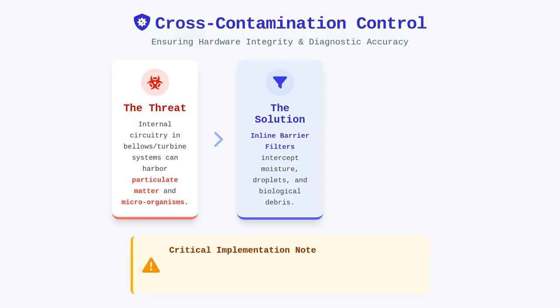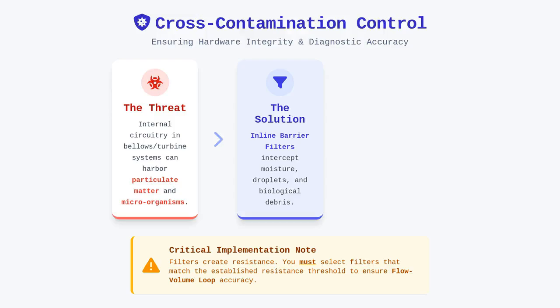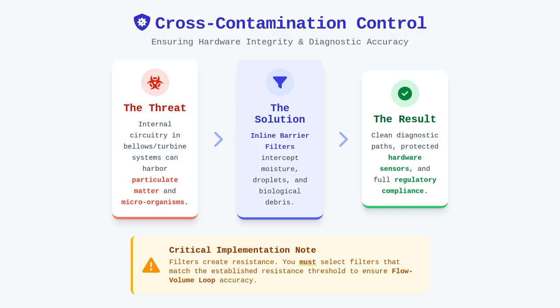It is important to remember that these filters create resistance, so you must select ones that meet the established resistance threshold for your specific diagnostic device to ensure the flow volume loop remains accurate. By creating this physical barrier, you maintain a clean diagnostic path and protect the long-term integrity of the hardware sensors. Furthermore, maintaining these configurations within legal diagnostic laboratory limits ensures that your lab remains compliant during any external quality auditing or safety inspections.